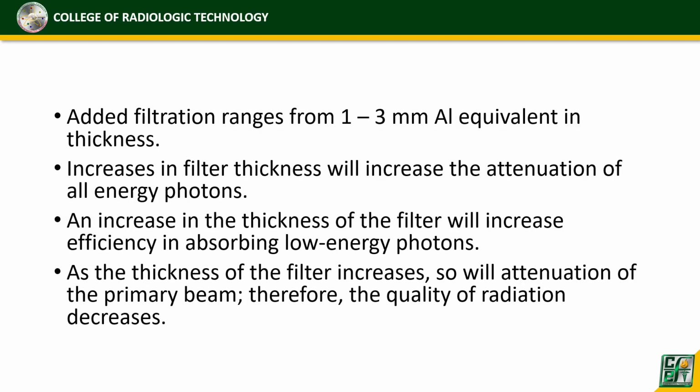Okay. So, added filtration ranges from 1 to 3 millimeter aluminum equivalent in thickness. Okay? So, increases in filter thickness will increase attenuation of all energy photons. Okay?